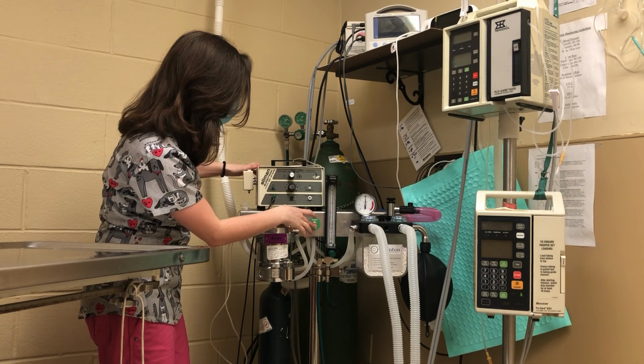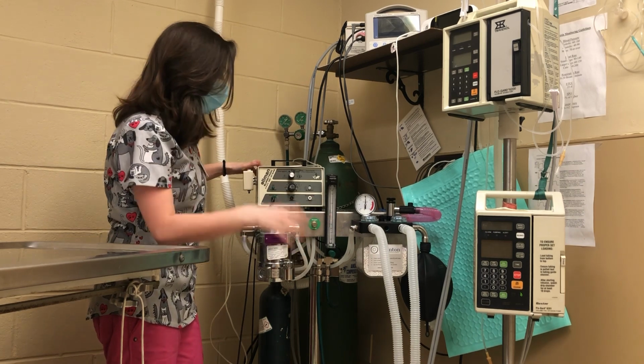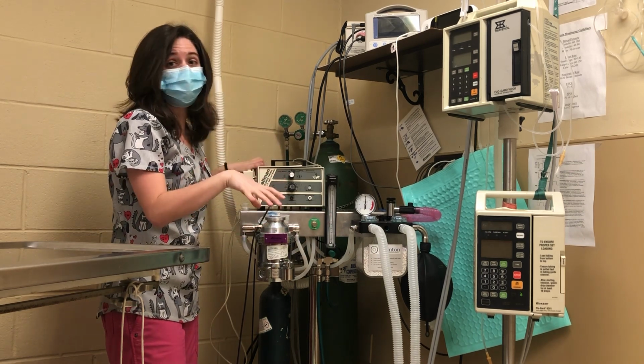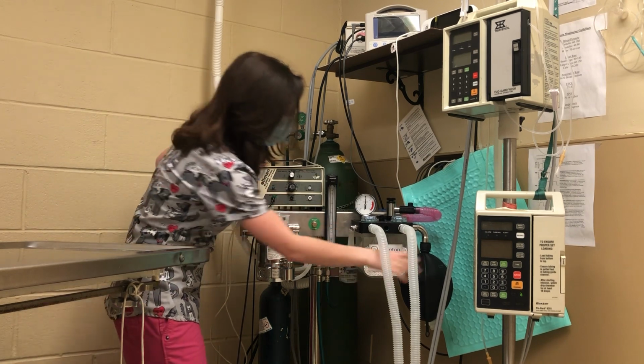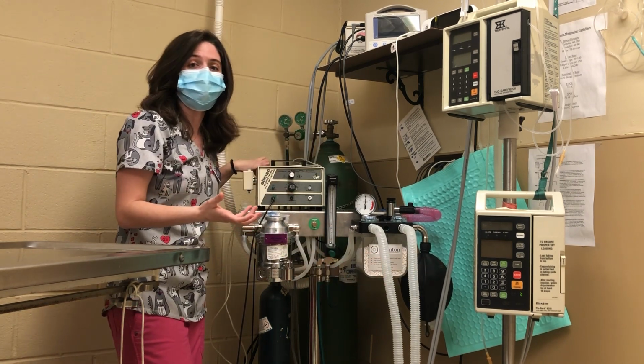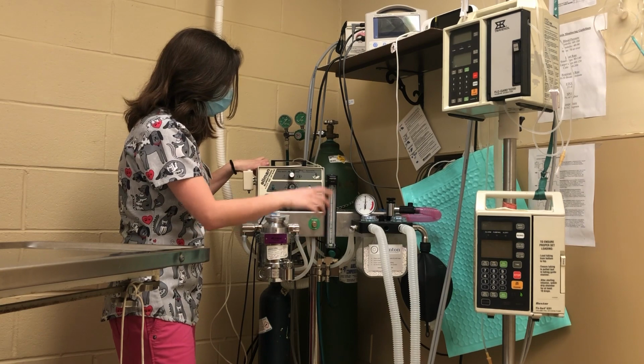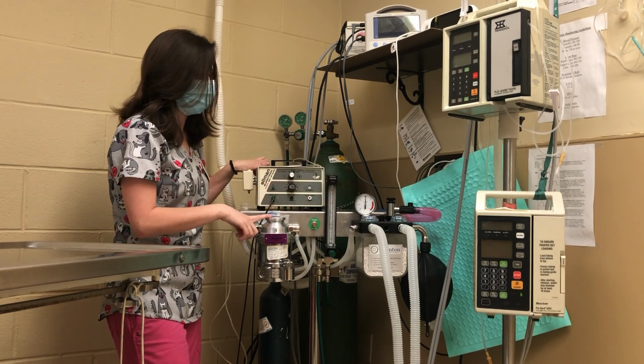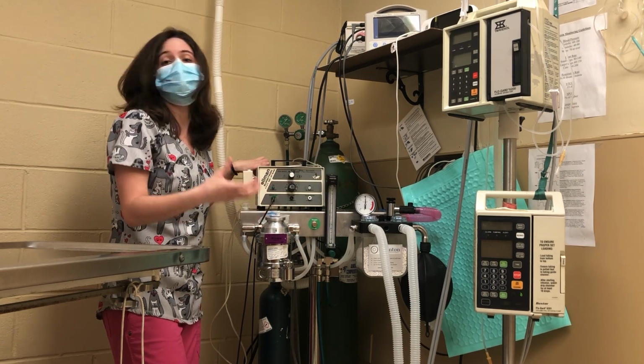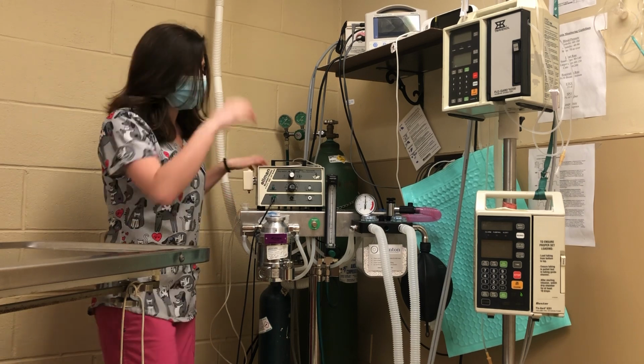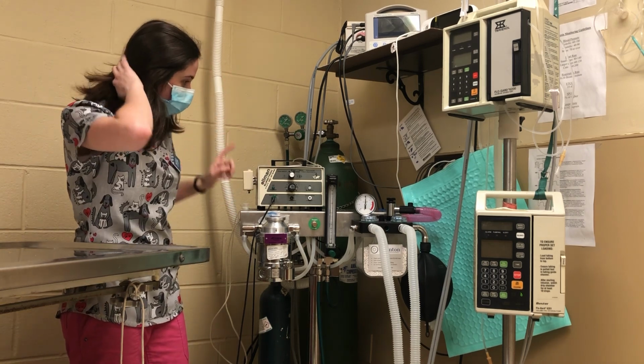Our oxygen flush valve here, if you press it, releases a large amount of pure oxygen right into the reservoir bag so that the patient can breathe that in. It also bypasses the flow meter and the vaporizer, so it's a quicker way of giving the patient a burst of oxygen. What else?